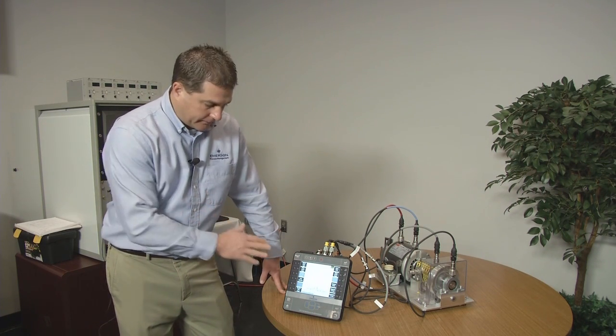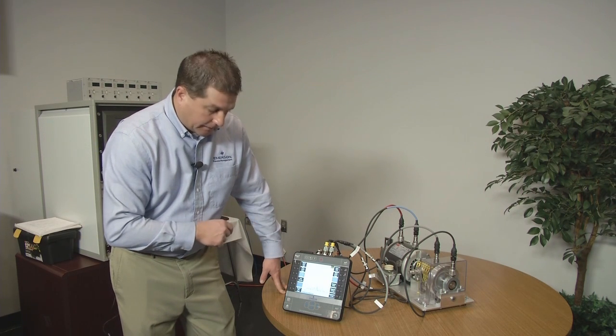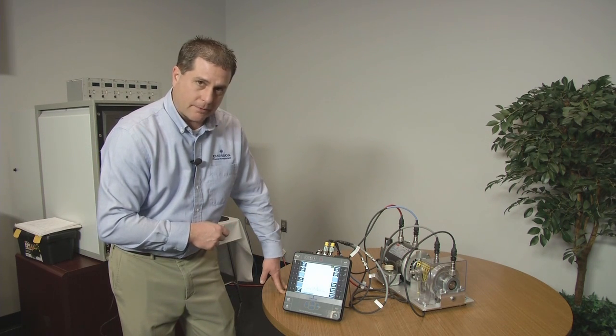It's marked at 59.45 hertz. And that is two times turning speed for this particular demo kit here. So I've already identified, marked the peak. The frequency seems to be correct for two times.